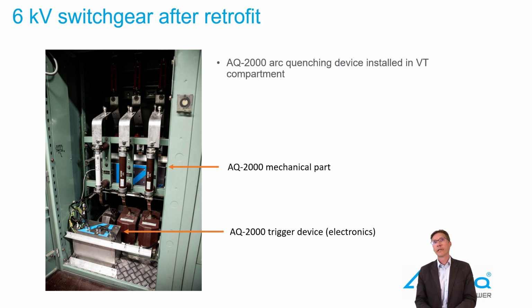And the next picture here shows the actual arc quenching device installation. Again, it was in this particular switchgear possible to fit it in the VT compartment. Sometimes you have space in the incoming sections. Sometimes you may extend the bus bar to go to the next section or extra section for the AQ2000, but VT compartments are quite often spacey, so to say. So here you see the actual mechanical operation part of the AQ2000, which is actually closing the 3 phases for the arc transfer. And we have the AQ2000 trigger device, which is the electronics below that. So the electronics is controlling the mechanical part, and the electronic part itself is controlled by the relays.